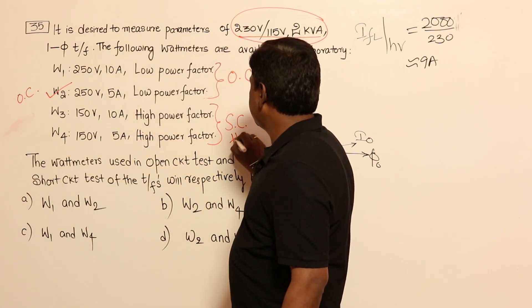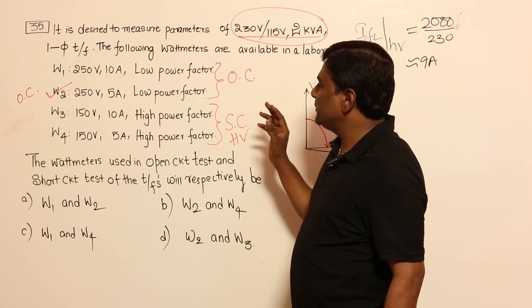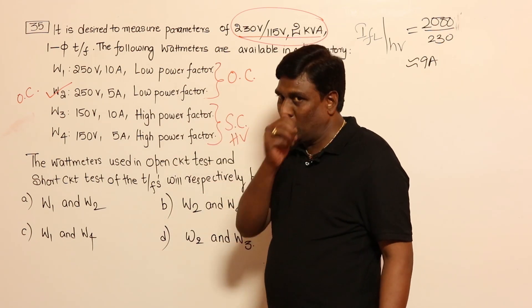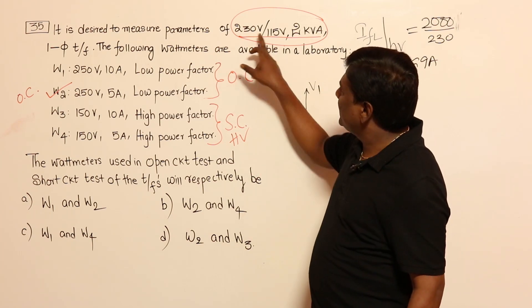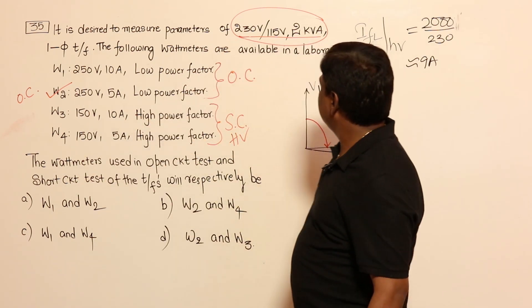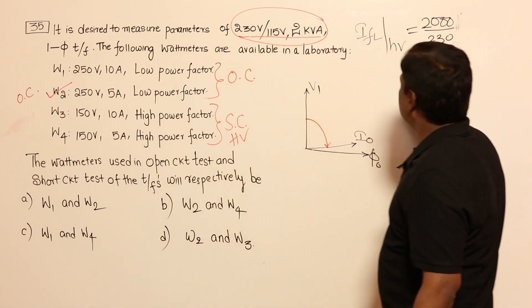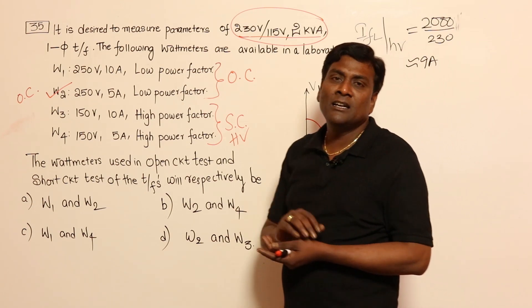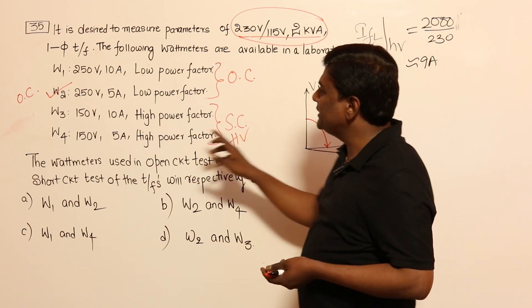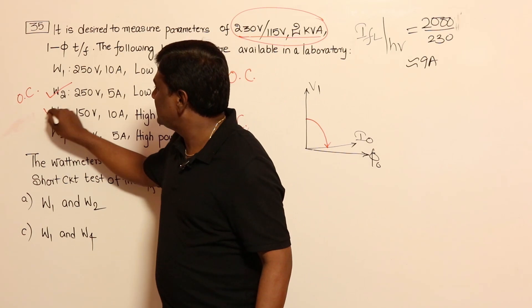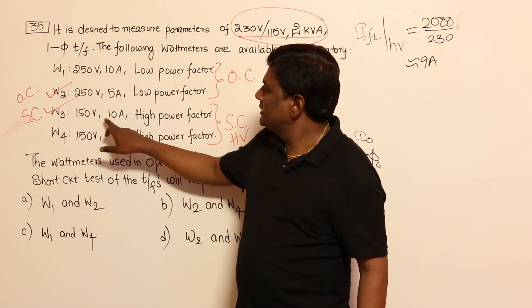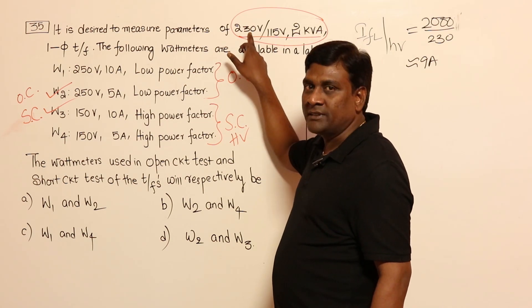SC test is also under HV side only. Don't think 115 is nearer to 150 — the relevant voltage here is the short circuit voltage, which is very small compared to rated voltage. 230 volts rated means the SC voltage is about 23 volts, which is nearer to the 150V range. Full load current on HV side is 9 amperes; SC test is conducted at rated current. So 9 amperes is nearer to 10 amperes — we select W3, with 10A and 150V ratings, for the SC test.